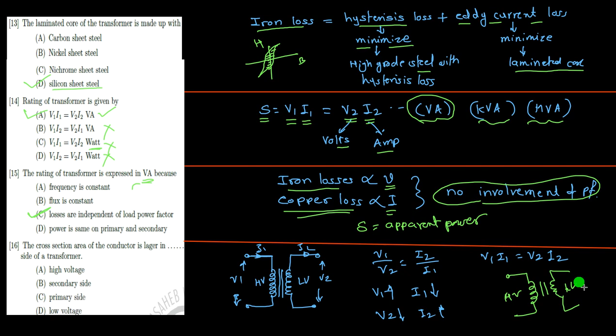Apparent power. The cross sectional area of the conductor is larger in which side of the transformer? So we know that in a transformer, whether it is step up or step down, one winding is a low voltage winding and one winding is the high voltage winding. Transformer is a dual device, you can make this the primary and this the secondary, or you can make this the primary and this the secondary. So primary or secondary may be HV or LV, but for the HV winding the current is less, for the low voltage winding the current is higher.